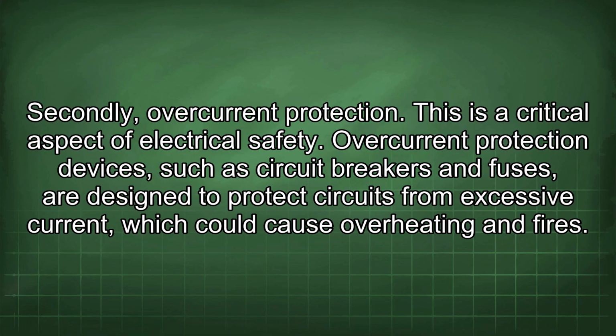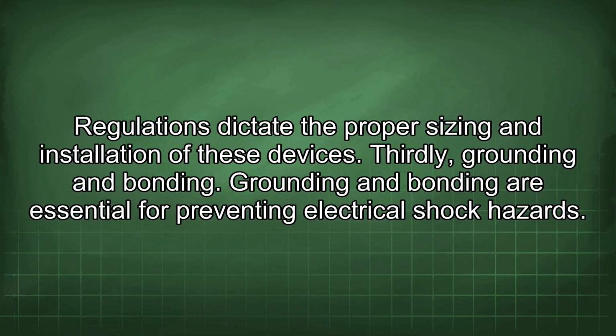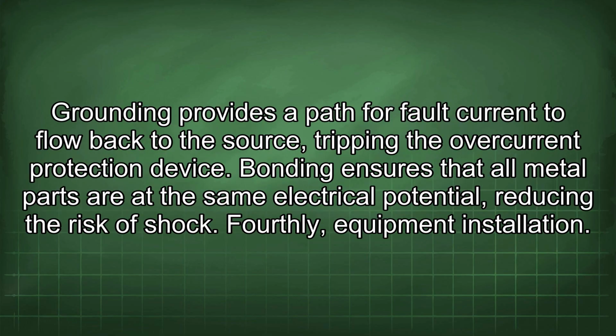Secondly, overcurrent protection. This is a critical aspect of electrical safety. Overcurrent protection devices, such as circuit breakers and fuses, are designed to protect circuits from excessive current, which could cause overheating and fires. Regulations dictate the proper sizing and installation of these devices. Thirdly, grounding and bonding. Grounding and bonding are essential for preventing electrical shock hazards. Grounding provides a path for fault current to flow back to the source, tripping the overcurrent protection device. Bonding ensures that all metal parts are at the same electrical potential, reducing the risk of shock.